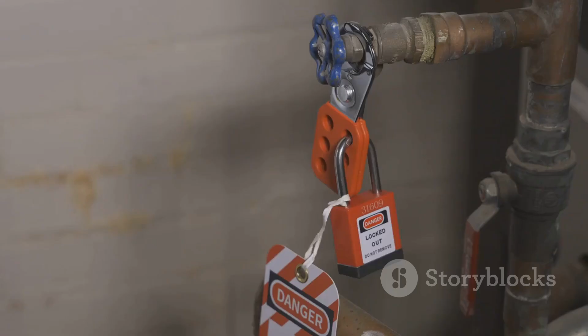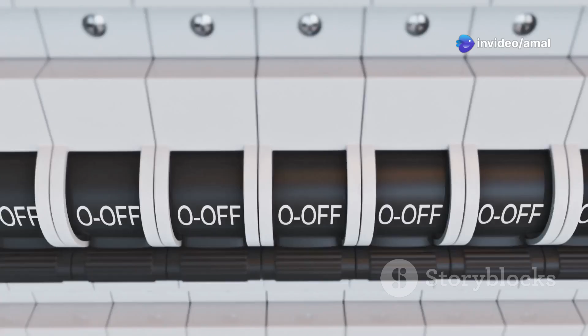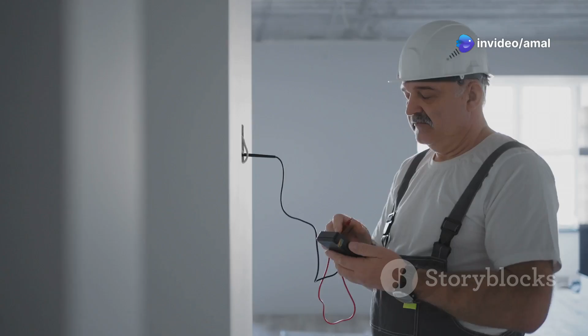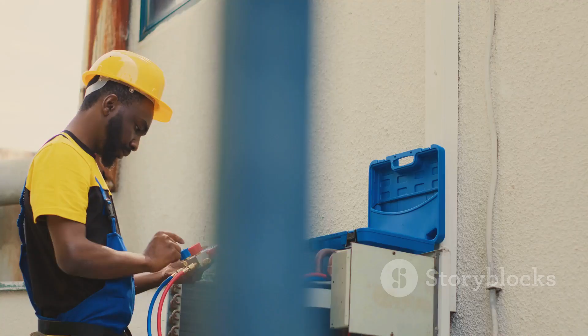The next step is to apply a lockout device to each energy isolating device. A lockout device is a physical lock that prevents the equipment from being accidentally turned on. Tags are then attached to the lockout devices to provide a visual warning that the equipment is being worked on. Before starting work, it's crucial to verify that the equipment is de-energized. This is done using a voltage tester or other appropriate testing device. Only after confirming that the equipment is safe to work on should maintenance or repair activities commence.